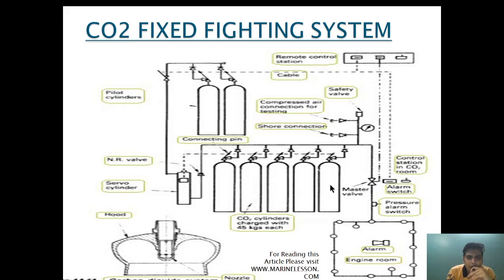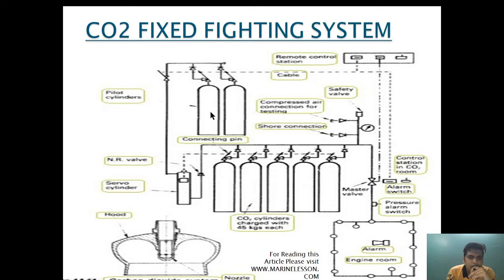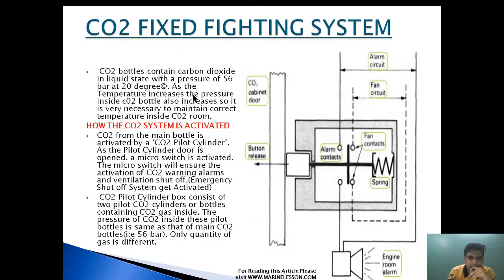Through the remote control panel, the pilot cylinder valve and the master valve are controlled. First, we have to activate the pilot cylinder. After the pilot cylinder is activated, the CO2 from here will go through this valve, which will be remotely operated by the remote control station. When the CO2 door is open, an alarm will go off indicating that the CO2 pilot door has been opened.